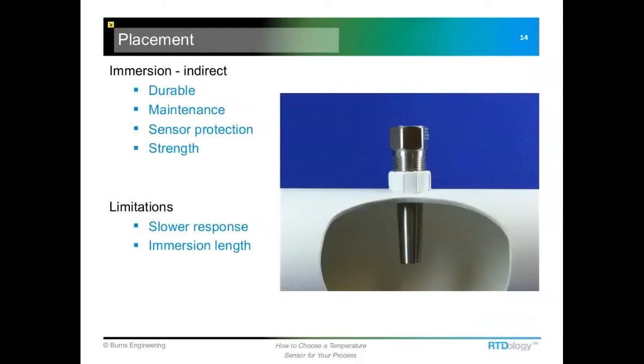If we were to add a thermal well into this process, then doing maintenance on the sensor becomes a lot easier, because the piping is completely sealed up. It provides extra protection for the sensor, a lot of extra strength to it, and I think for our process here, this is going to be the direction we're going to go.